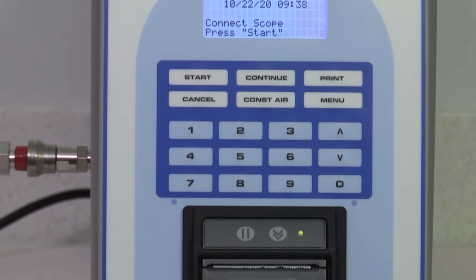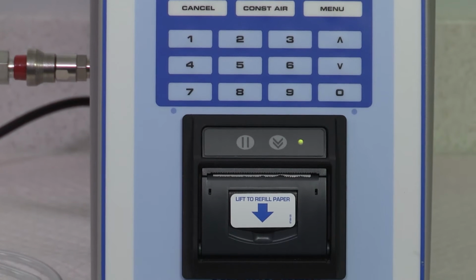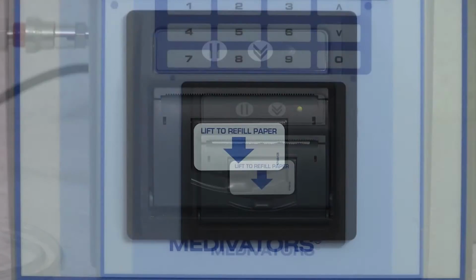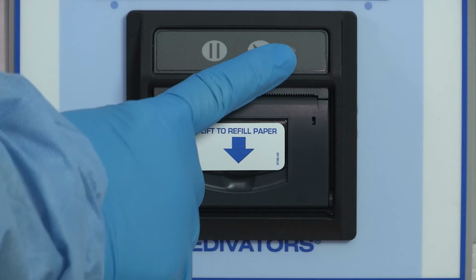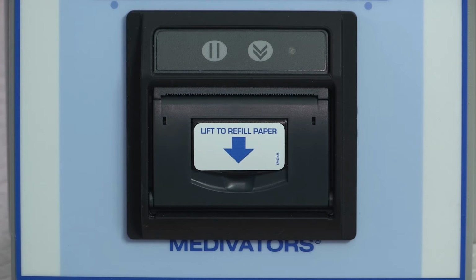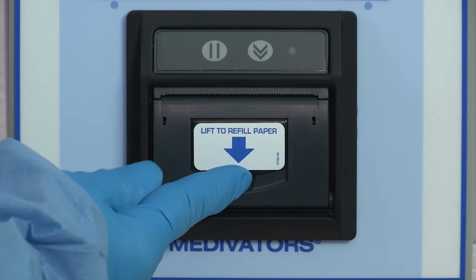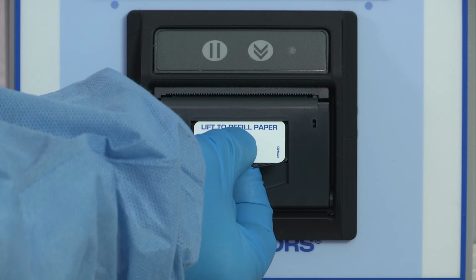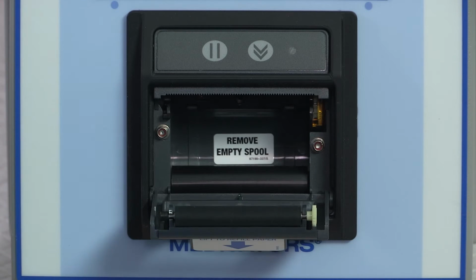Another feature of the VERISCAN Leak Tester is the built-in printer. The printer automatically detects when the paper roll is empty and flashes a small LED light on the front of the printer. To load or replace the printer paper, first gently pull the lever on the front of the printer paper access door upward until the lid is released from its lock position. To avoid damage, do not use excessive force.